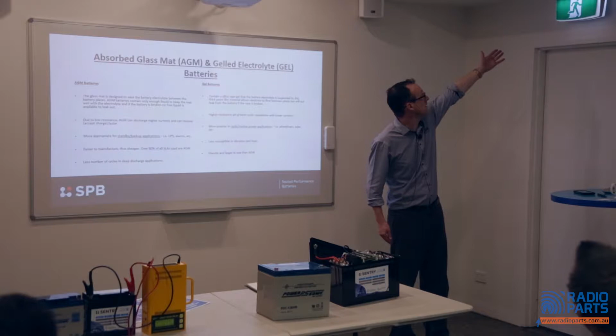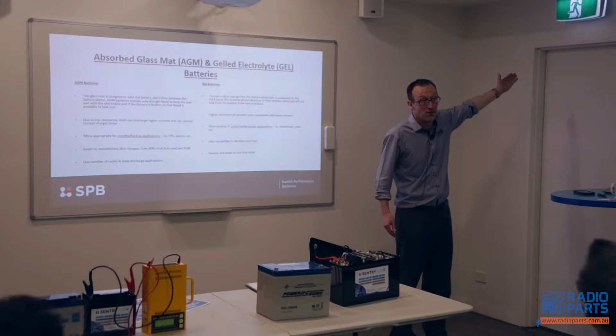In the event of a mains fail, there's a battery inside of there, and the law states with emergency lights that they have to hold themselves up for 2 hours. Because if we've got a fire or something, by law, you've got to give 2 hours worth of good grace for everybody to get out of Dodge. So that there is a typical backup application, or network power as it's called.